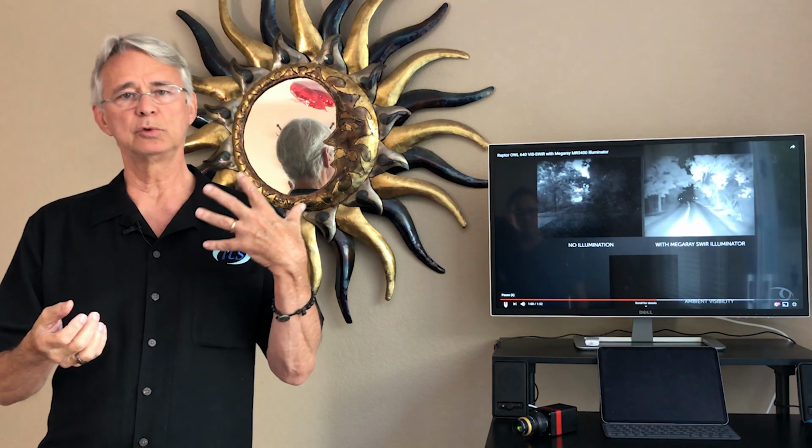When you measure temperatures, there's a couple of ranges. The cameras are calibrated. For example, the first calibration might be -20 to 120 degrees C, and that would measure temperatures in those ranges. If you want to go to higher temperature ranges, you can go all the way up to about 800, 1,000 degrees C with a long wave camera. If you want to go higher, you could use a short wave camera and get all the way out from 350 degrees C all the way up to about 3,000 degrees C. So when you check out our website, just think about your temperature range if you're going to measure temperatures with your IR cameras or not.